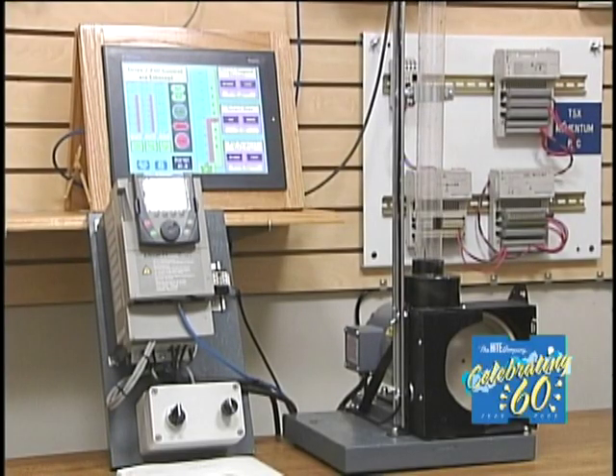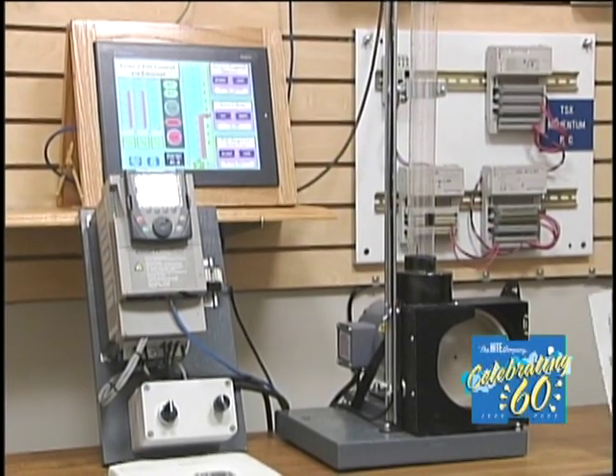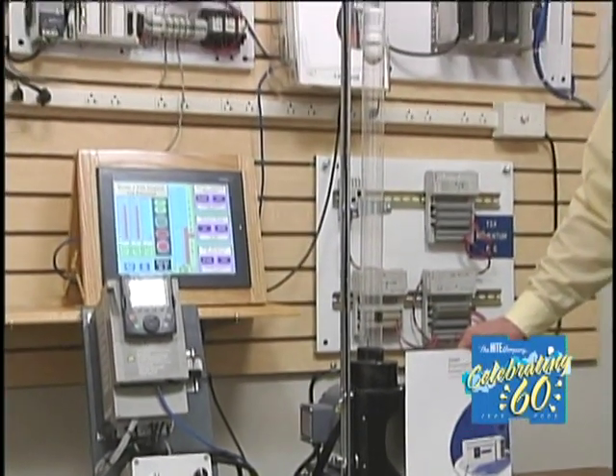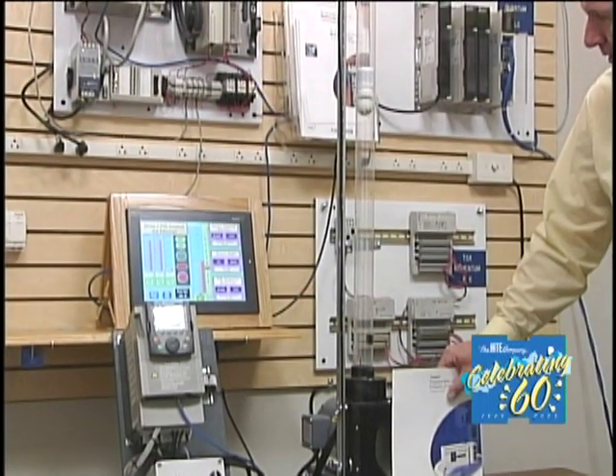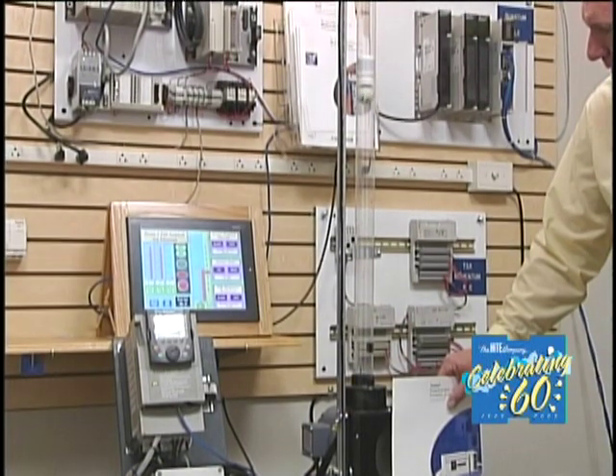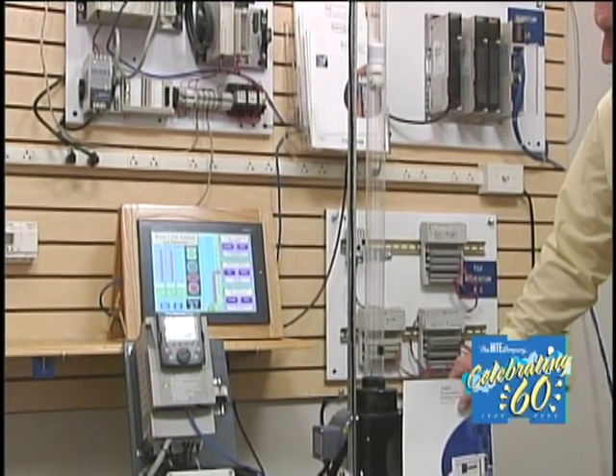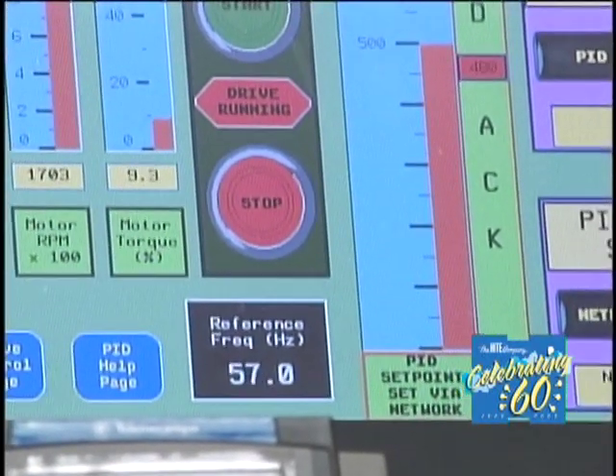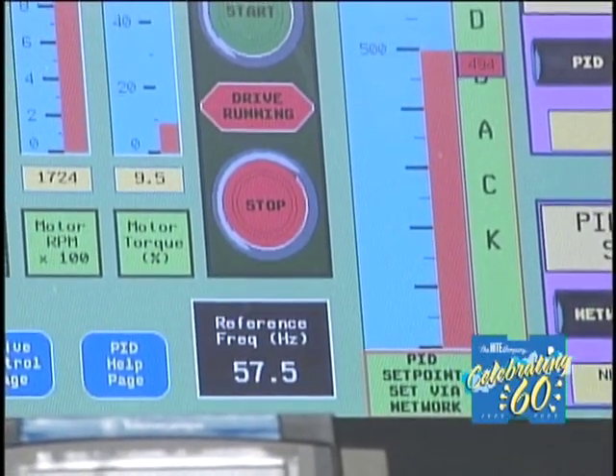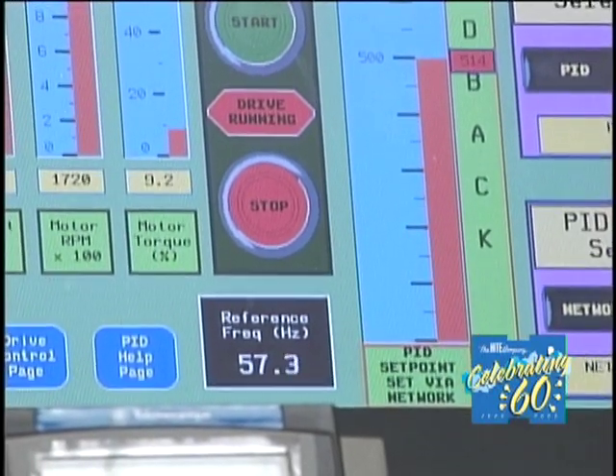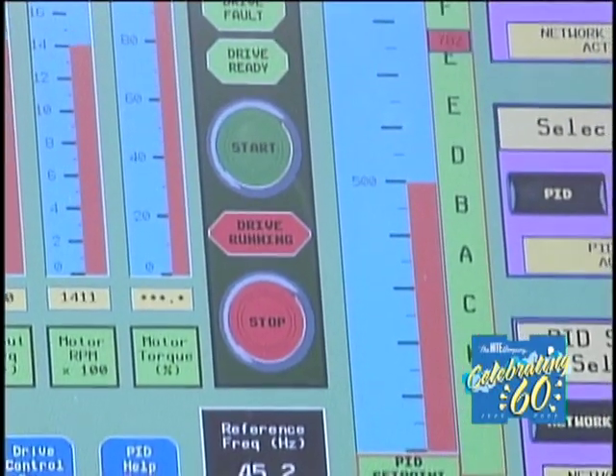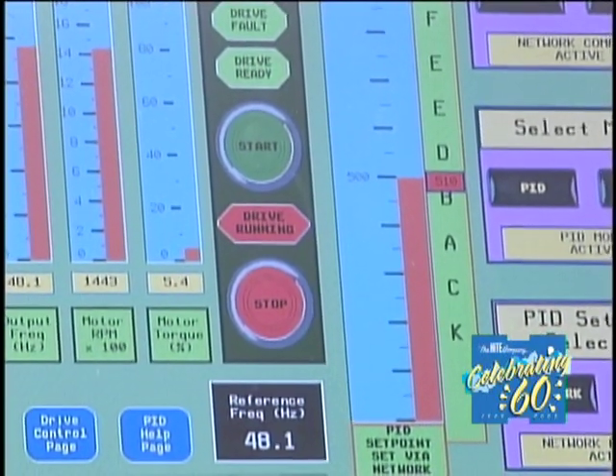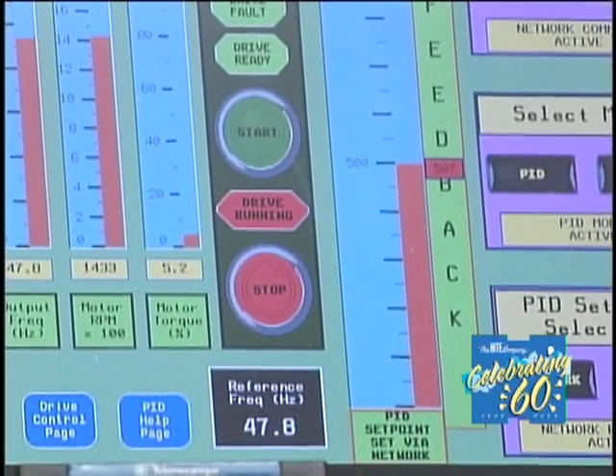Now we're demonstrating how a PI controller can compensate for a change in airflow. I'll place my hand over the fan. If you're able to see the screen, you can see that the drive is now running faster to make up for the loss of airflow. Now we'll abruptly pull that away. It's kind of an extreme situation, but the PI controller caught that — which it should do.